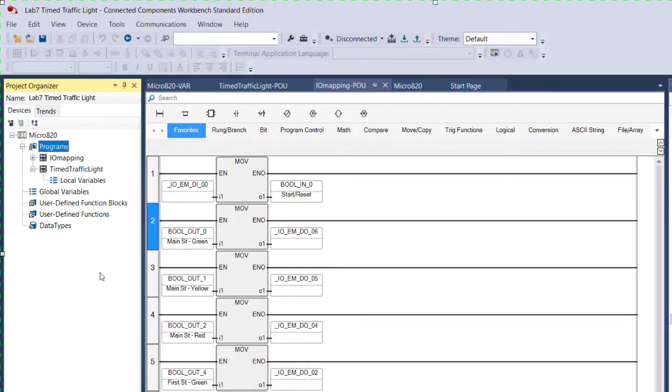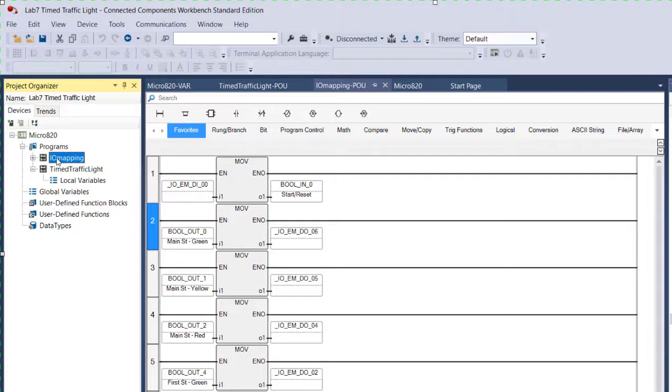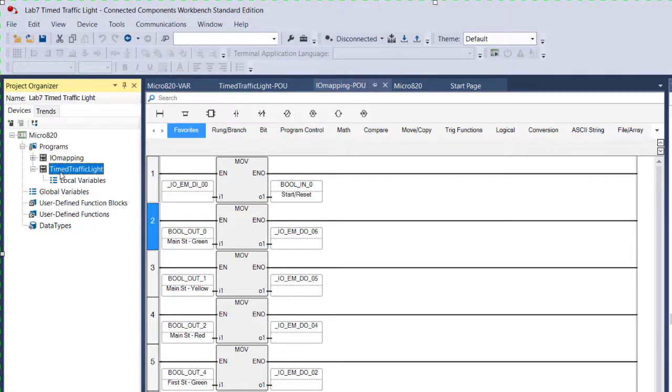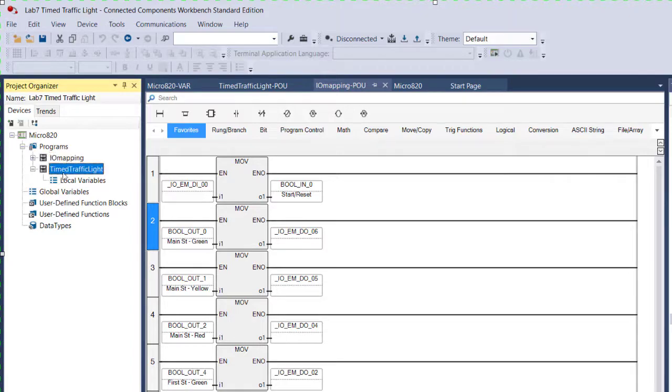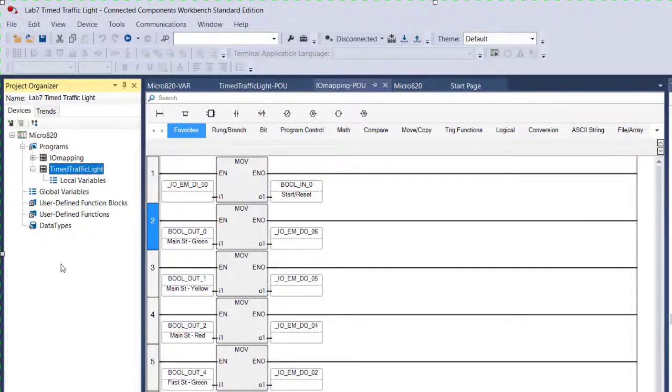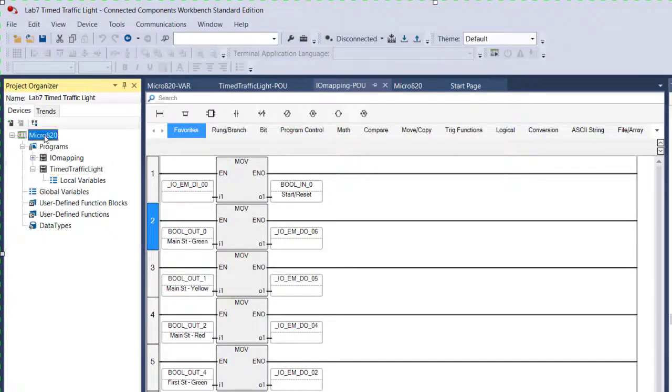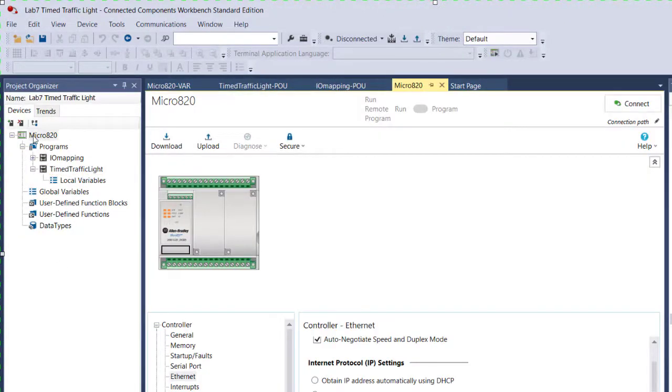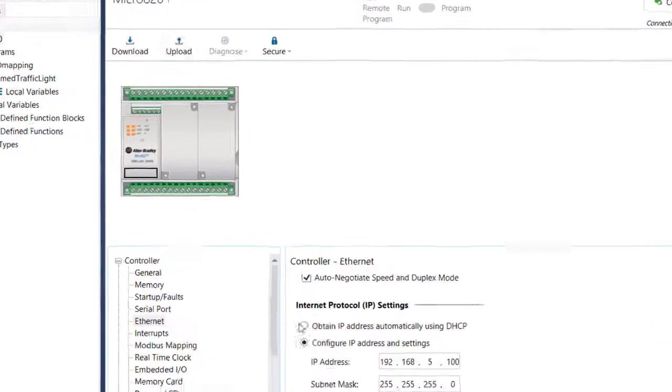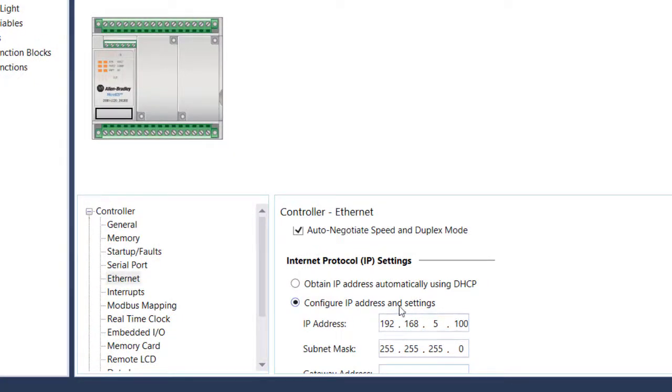When I download this program to the PLC, both of these programs will get downloaded automatically. The PLC will simply run through the I/O mapping program, all those rungs, and then it'll run through all the rungs of the timed traffic light, and it'll just run through those two programs over and over again. It'll do them in sequence. It'll do this program first, followed by this program second. So now that I've created the two programs and I'm ready to download them to the PLC, I've got to make sure that this Micro 820 is configured to the right Ethernet address, so we don't override the existing Ethernet address on the PLC. And we also need to change the IP address to the Ethernet port on your computer, so that the first six digits are the same.